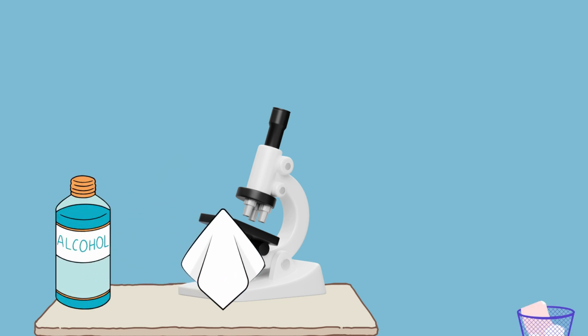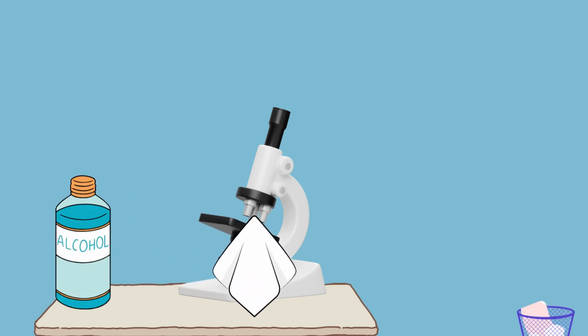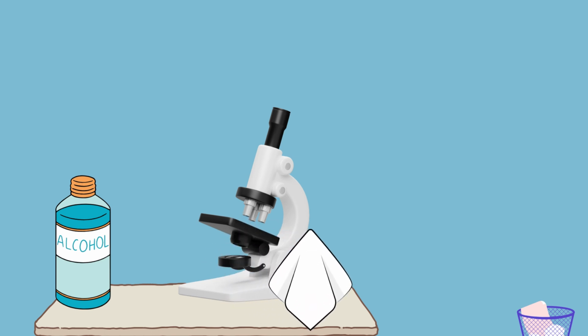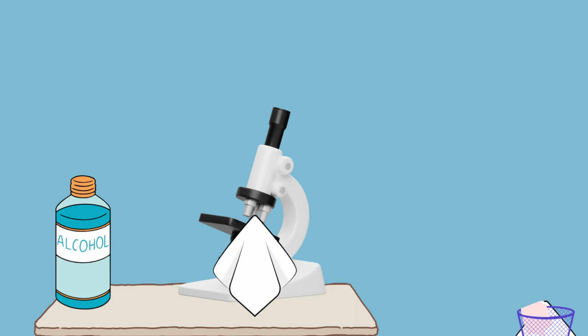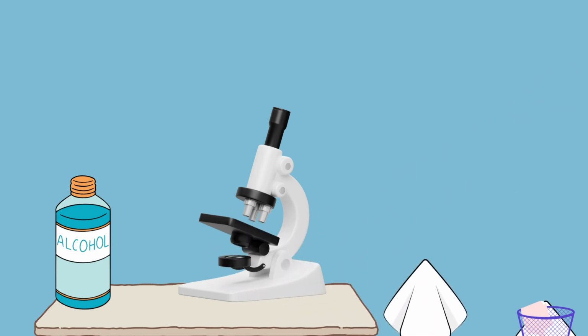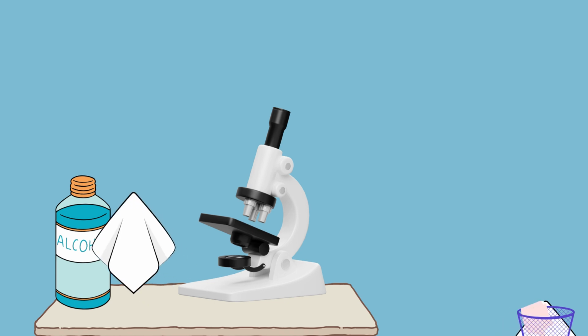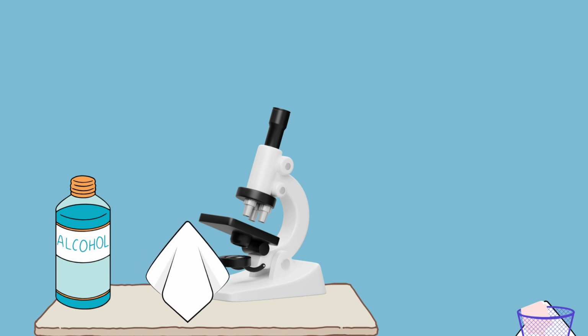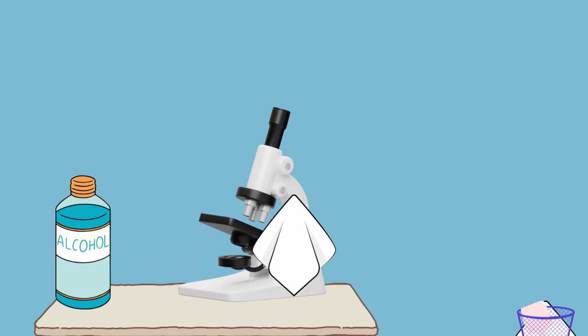Next, 70% isopropyl alcohol should be applied to lens tissue or a swab and gently dragged across the lens. A fresh lens tissue should then be obtained to remove any remaining cleaner off the lens. Using the 70% isopropyl alcohol again on a cloth, the surface of the microscope should be wiped and disinfected. This includes the focusing knob, the nosepiece, the stage handles, and other frequently touched surfaces.